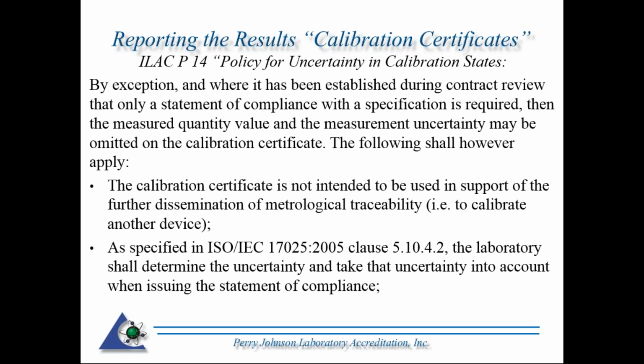If that thermometer, let's say you're a calibration lab and you send your thermometer in to another calibration lab, maybe to the manufacturer that has relatively small uncertainties that would benefit you, but you're going to use that thermometer to calibrate other thermometers. In that case, the uncertainty has to be reported.